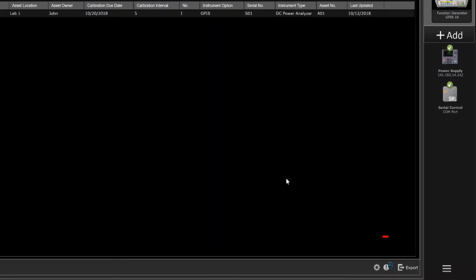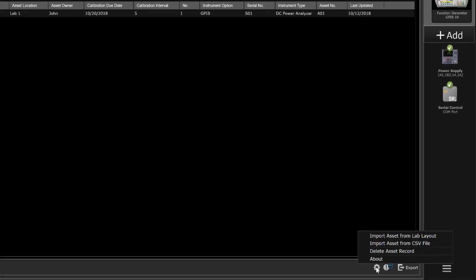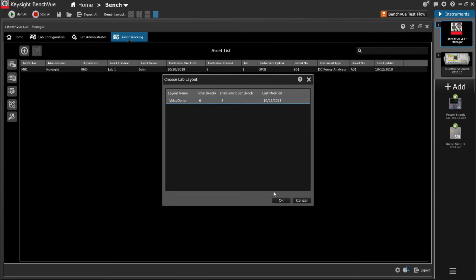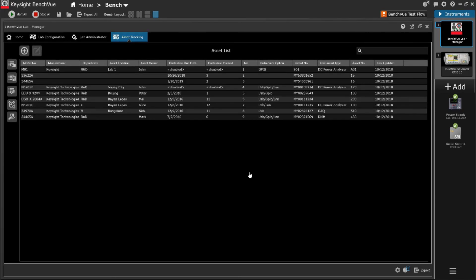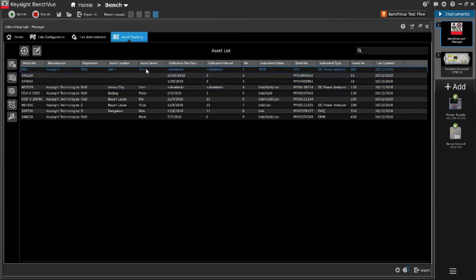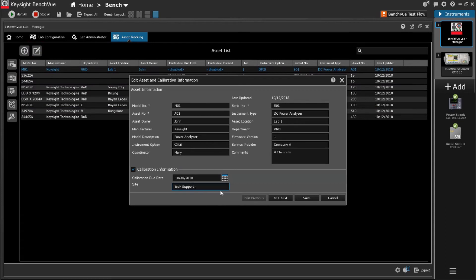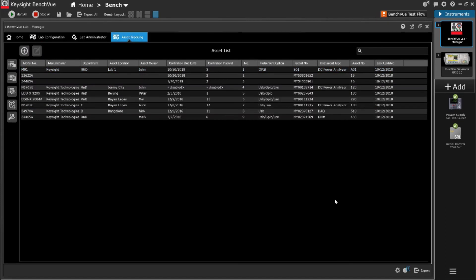It enables a quick inventory by importing previously configured instruments into an asset tracking database. You can view individual instrument calibration information and see upcoming calibration intervals.